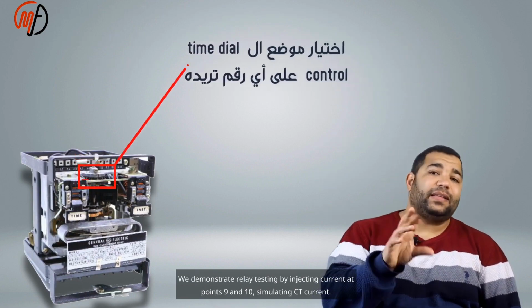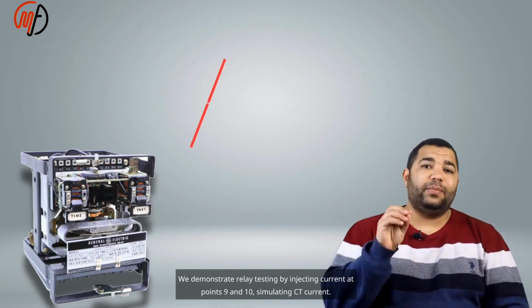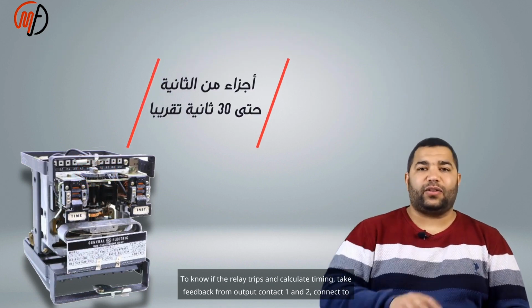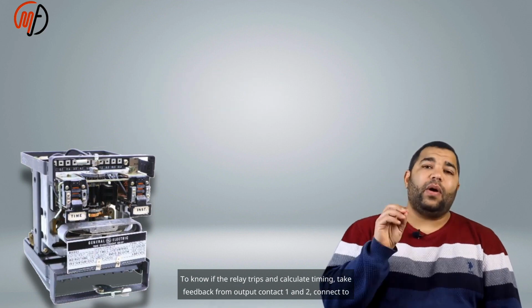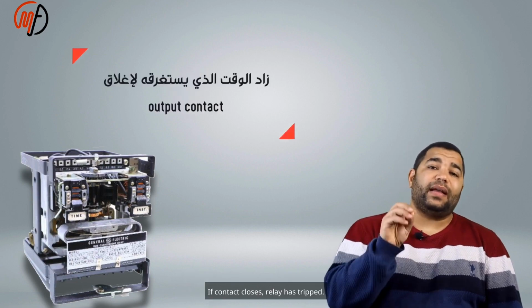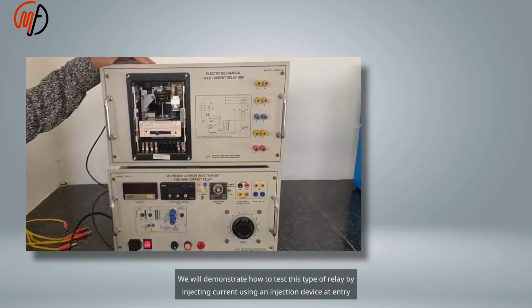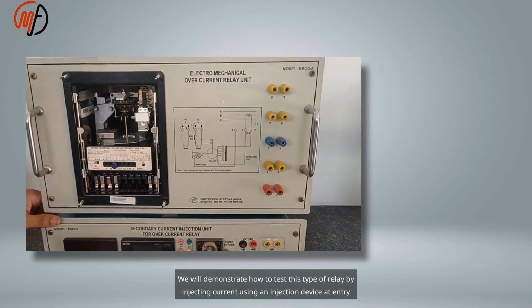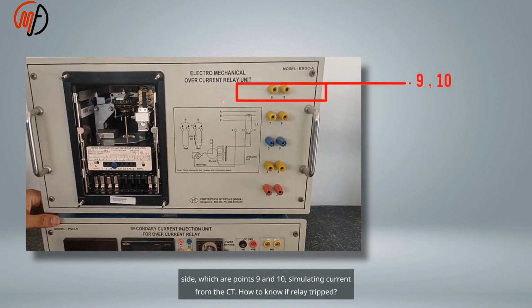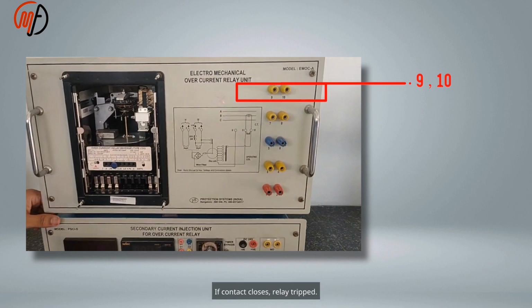We demonstrate relay testing by injecting current at points 9 and 10, simulating CT current. To know if the relay trips and to calculate timing, take feedback from output contacts 1 and 2 and connect them to the injection device. If the contact closes, the relay has tripped. Set the current value for relay operation. We will demonstrate how to test this type of relay by injecting current using an injection device at the entry side, points 9 and 10, simulating current from the CT. How do we know if the relay tripped, and how do we time the trip? Connect output contacts 1 and 2 to the injection device. If the contact closes, the relay tripped.